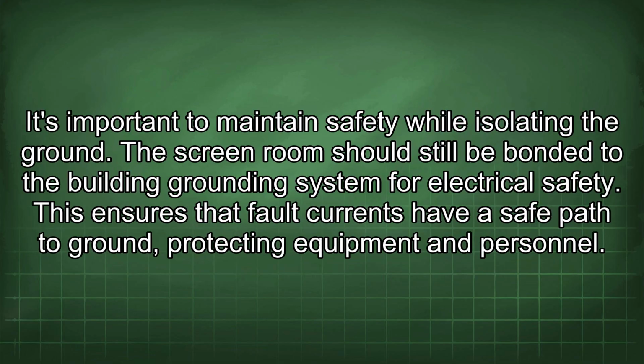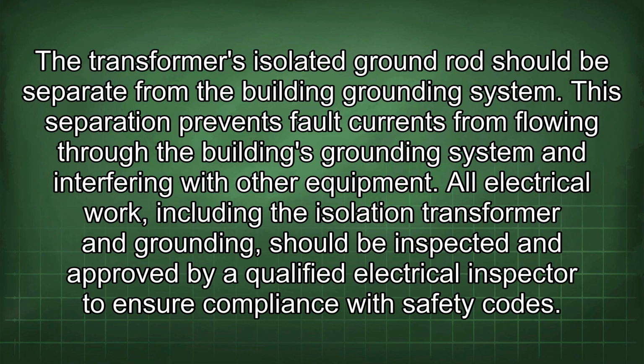It's important to maintain safety while isolating the ground. The screen room should still be bonded to the building grounding system for electrical safety. This ensures that fault currents have a safe path to ground, protecting equipment and personnel. The transformer's isolated ground rod should be separate from the building grounding system. This separation prevents fault currents from flowing through the building's grounding system and interfering with other equipment.